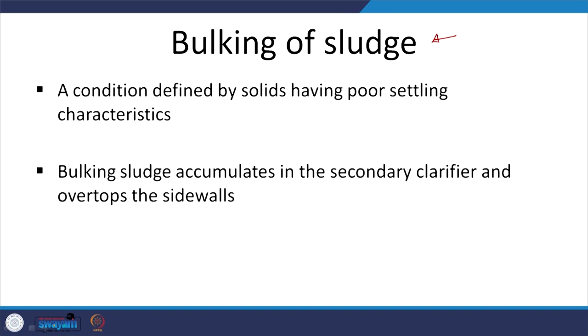Sludge bulking is one common factor that ruins many Indian treatment plants and quite a lot of plants worldwide. In the aeration tank, microbes degrade the waste; when they go to the secondary settling tank or clarifier, you need floc-forming bacteria that settle down. Depending on F/M and theta_c, you may instead have sludge that does not settle — bulking of sludge.